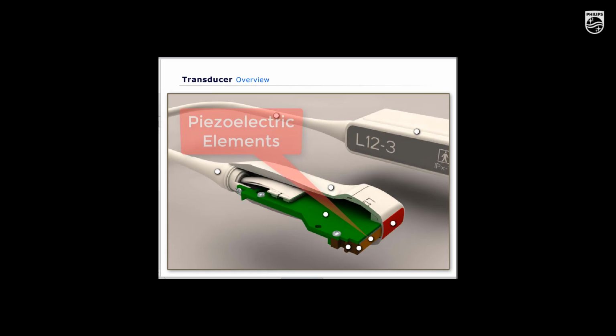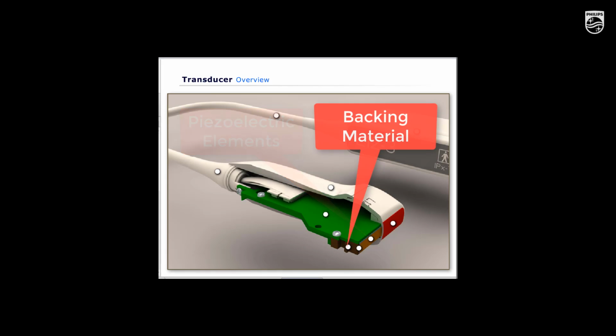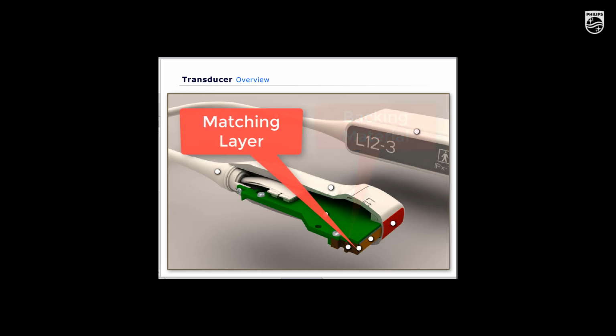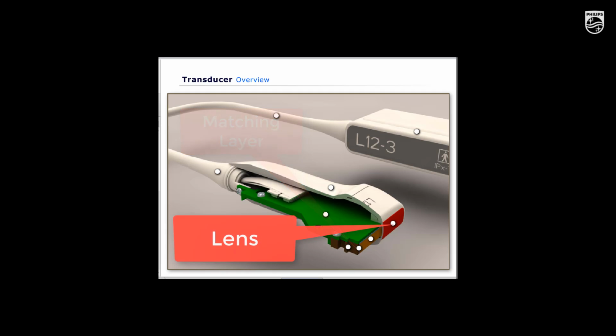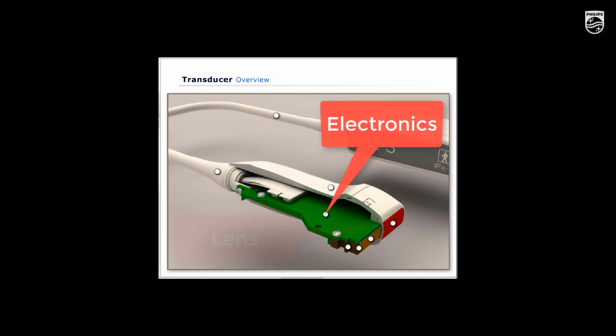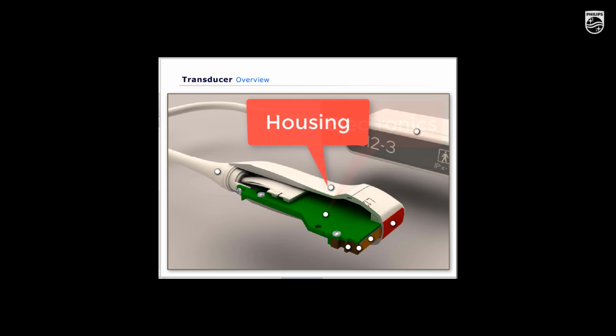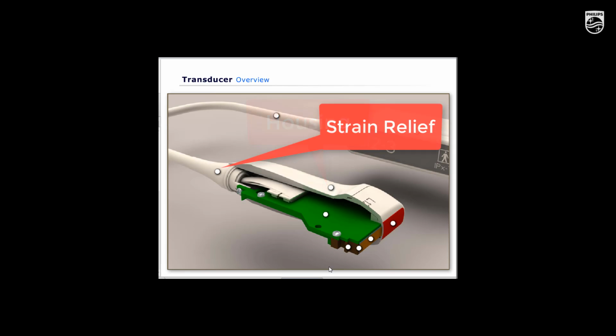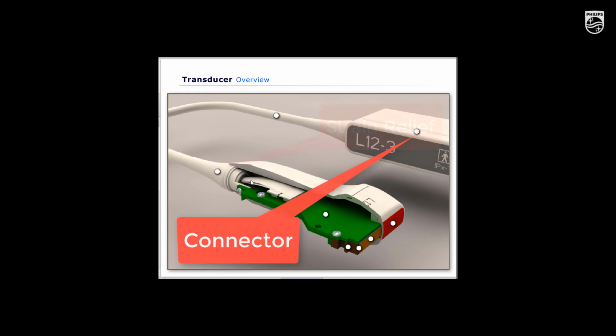An ultrasound transducer consists of the following parts. The piezoelectric element converts electrical energy into sound and vice versa. Backing material damps the pulse and forces the wave into one direction. Matching layers are used to bridge the different acoustic impedances of the piezo elements and tissue. The lens is used to focus the beam and also as the footprint. Circuit boards inside contain electronics for various functions. Housing protects the inside. Strain relief is used to prevent the cable from pulling off the connector and transducer head. The connector physically connects the ultrasound system.